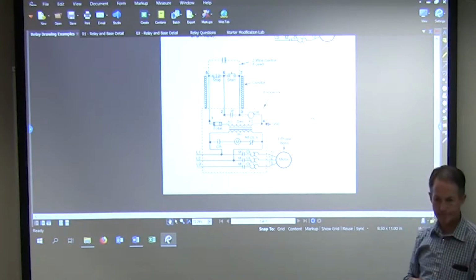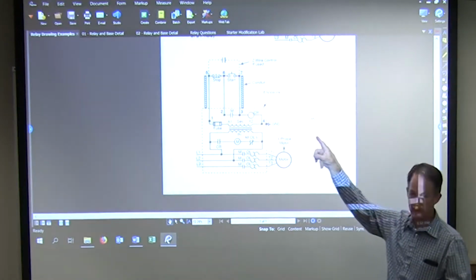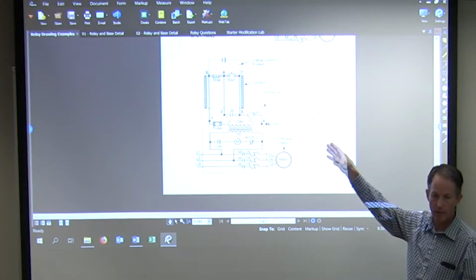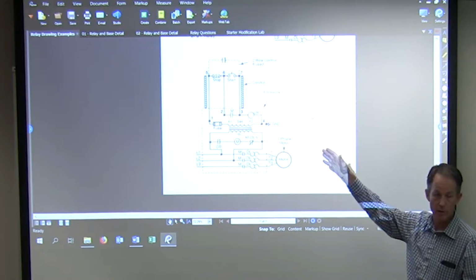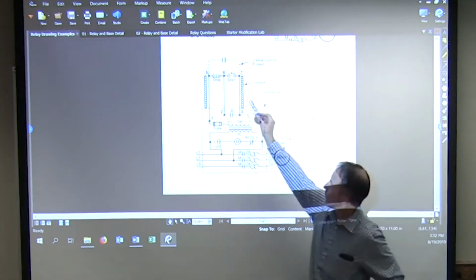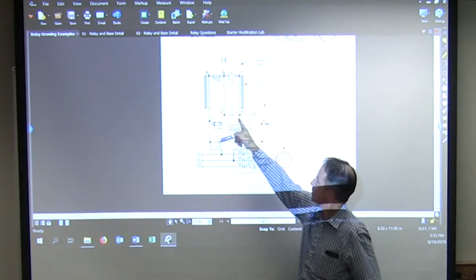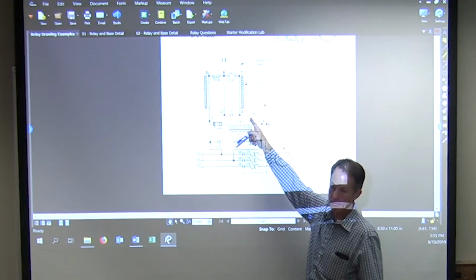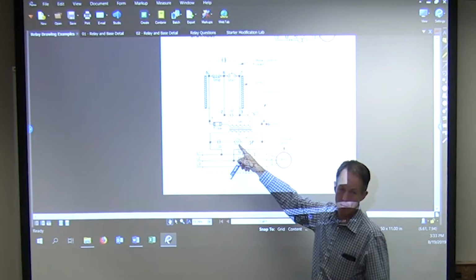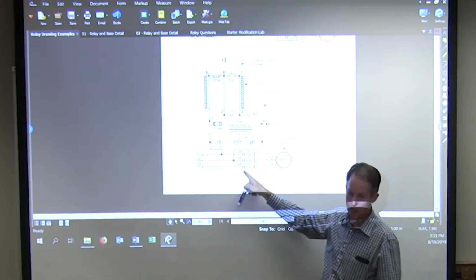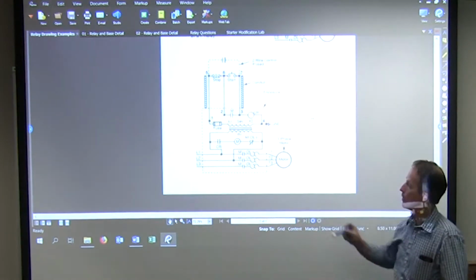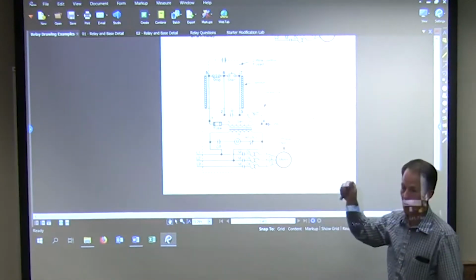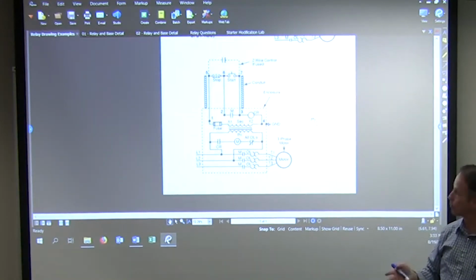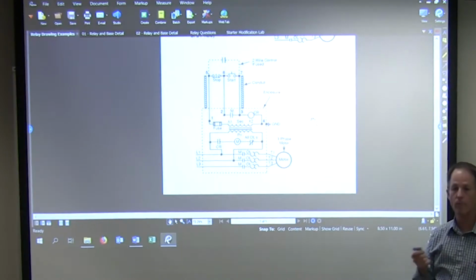How do I stop this? Stop button. Okay. Pressing the stop button, where does it stop our flow of current? At 5. So 5 is basically the place where it stops. Before, we were going 6 to 2, that was holding us. So then it went all the way through, but now I have no voltage there. So CR de-energizes, the contact opens, the main contactor de-energizes, those contacts all open, and the motor turns off. We also open here, so if I let go of my stop, I'm back where I first was, where 6 and 2 have voltage there, ready to go. Okay.